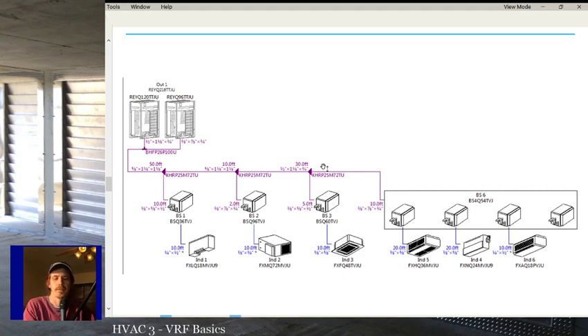You're generally going to have at least one variable speed compressor in every outdoor unit. You're going to have another variable speed compressor or standard compressor. Usually a lot of the outdoor units have two compressors because we're usually talking bigger systems on VRF. On heat recovery, you'll have branch selector boxes, which I have a picture up now showing that. This is a piping diagram that you would have to follow if installing this particular Daikin VRF. This is how it would look. And you'll have indoor units, and then you'll have the little Y kits that split the lines.